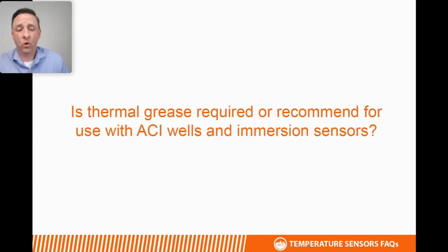Is thermal grease required or recommended when using ACI immersion sensors and wells? No, we don't require it. When you order new sensors and wells from us, it's really not needed because there's a very snug fit between the sensor and the well. We do recommend using thermal grease if there's a retrofit or you're putting a new sensor into an existing well that's not a perfectly snug fit, like if there are any gaps from the well being too big of a diameter. All of our probes are a 1/4 inch diameter, so if you've got a well that takes a 3/8 probe, or it's a little too long, we recommend using the thermal grease to fill that space.